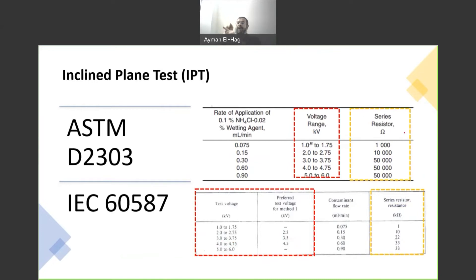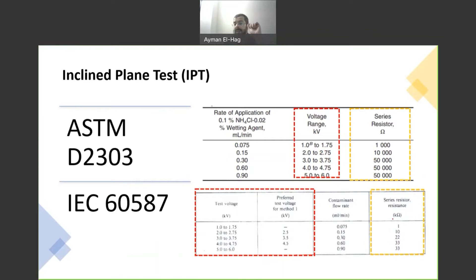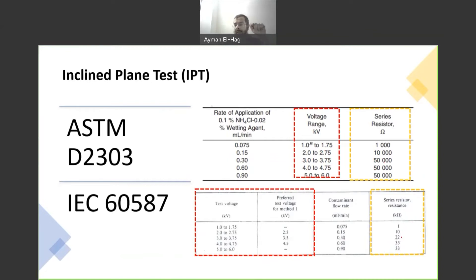Then we have the series resistor to limit the dry band arcing. This is one of the few differences between the two standards. At lower voltage levels, both use the same limiting resistor. But at higher voltage levels of 3 kV and above, ASTM uses only 50 kΩ resistance, whereas the IEC standard uses 22 kΩ and then 33 kΩ. This is one of the key differences between the two standards.